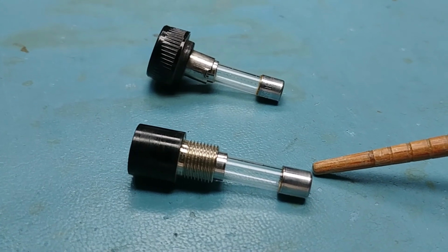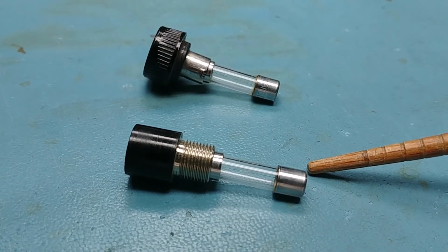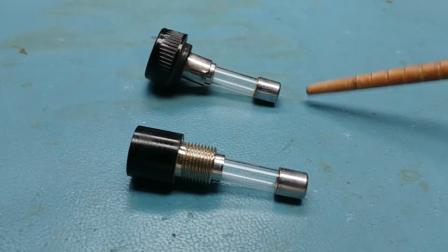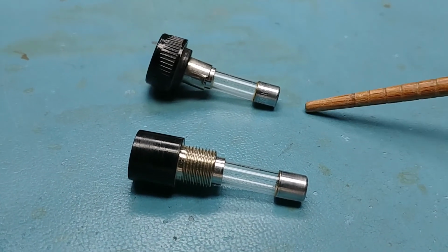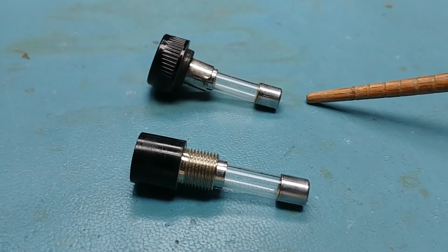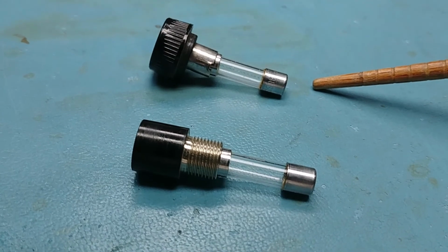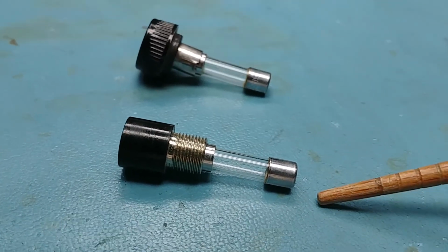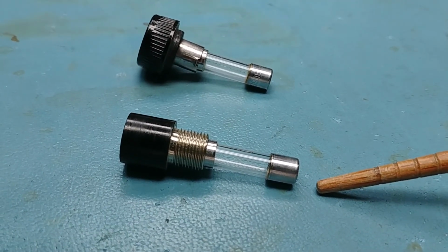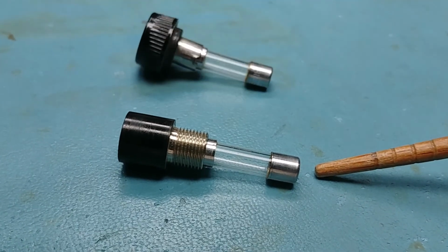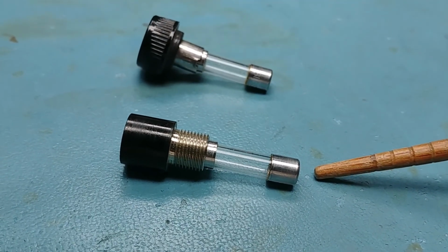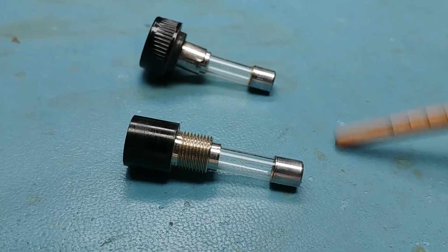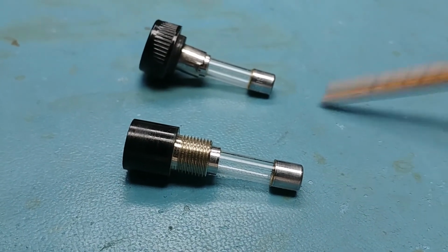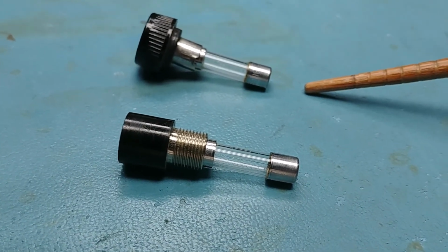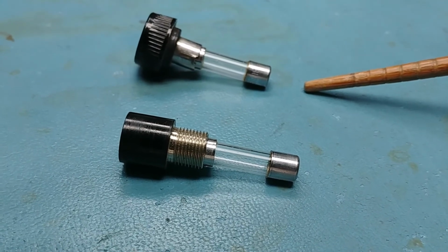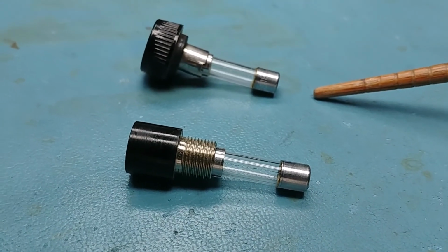This one actually has a screw head on it. It came right out because the body was not turning around inside the chassis like this one was. So both these fuses are good. They're both the same, with the same ratings, 250 volt by 2 amp and another 250 volt by 2 amp. This is actually supposed to be a 2.5 according to the outside of the chassis, so that tells me somebody's been in here and has changed these and just used the same fuse for both positions, which is fine. It's always better to underrate a fuse than it is to overrate a fuse.